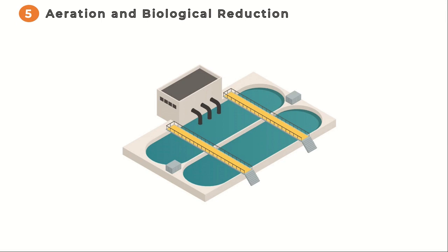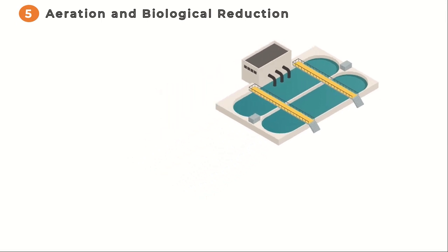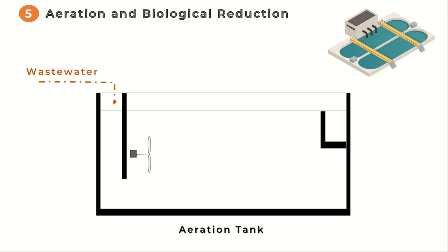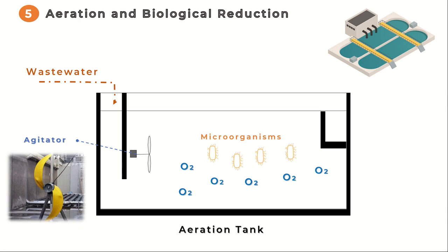The fifth step involves aeration and biological reduction. The wastewater is mixed with air and introduced to biological treatment units such as activated sludge or trickling filters. Microorganisms in these units break down organic matter, converting it into harmless byproducts, which reduces the pollutant levels in the wastewater. Agitators play a crucial role in the effective operation of anoxic tanks, ensuring proper mixing of wastewater and oxygen within the tank, which helps to remove pollutants and improve water quality.